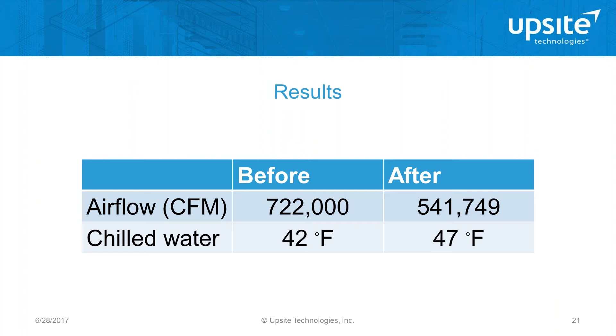But what actually changed dramatically is the power utilization for the fans, which reduced dramatically, while the IT load has gone up - that's where the efficiency gains have been. Absolutely, and I think that's probably quite conservative - I'd imagine there were significant chiller plant efficiencies as a result of raising that chilled water temperature. So yes, I'd take this as a conservative demonstration.